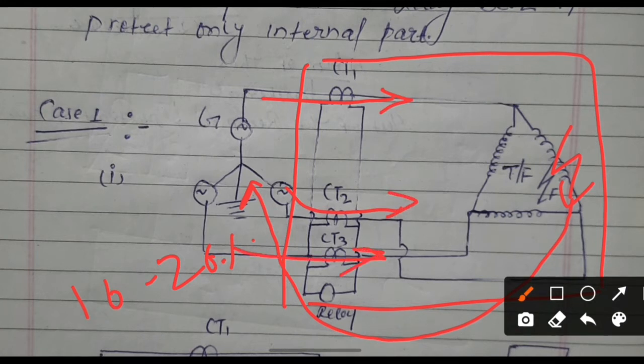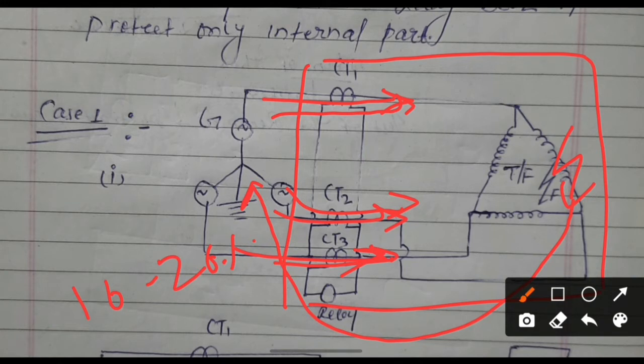At this time some positive sequence current and some negative sequence current cancel, but the zero sequence current flows through these CTs. So the relay will sense the current. If we are connecting the restricted earth fault relay on the delta side, we set the rated current and tripping current at 10 to 20 percent of rated current. Due to the zero sequence current the relay will sense and give the tripping command to the circuit breaker, and the circuit breaker isolates the transformer.